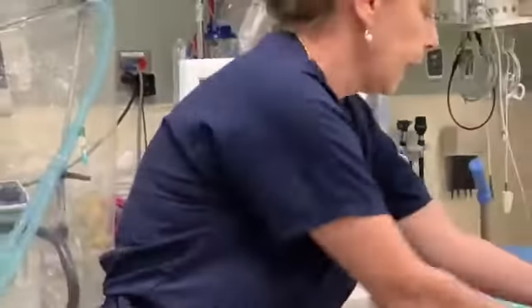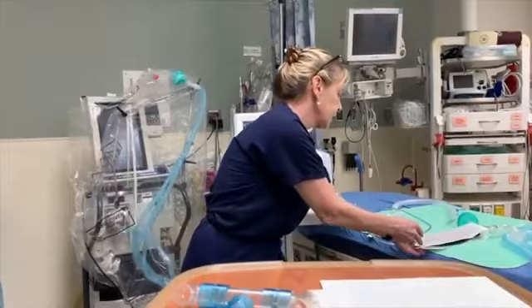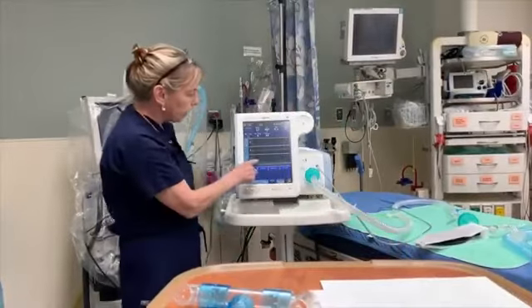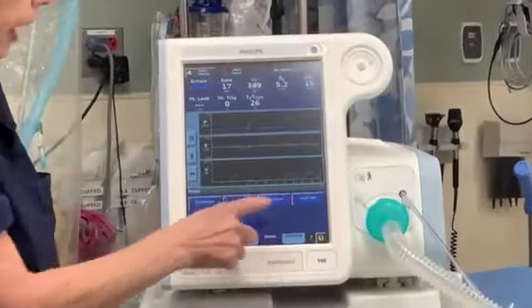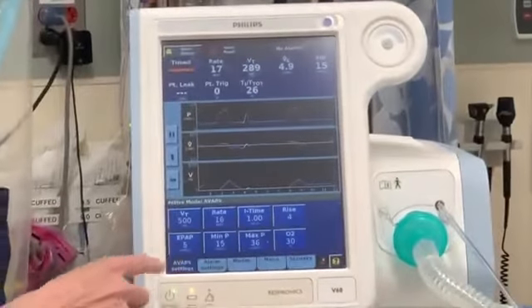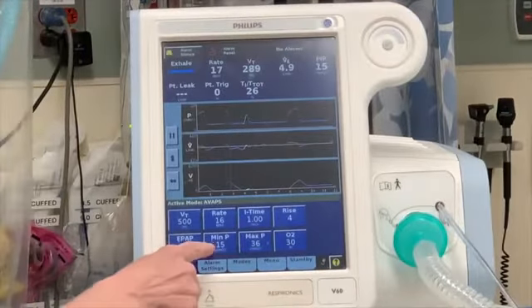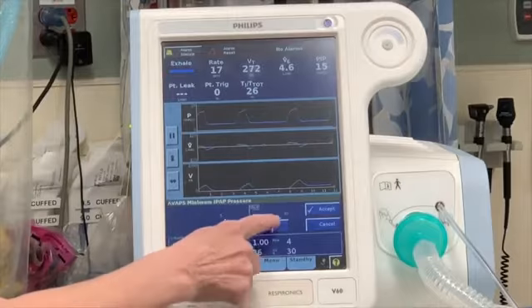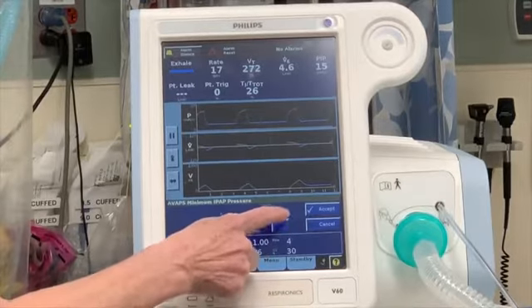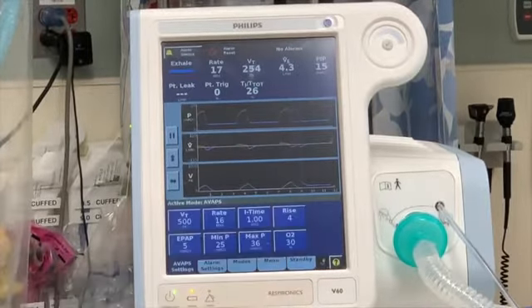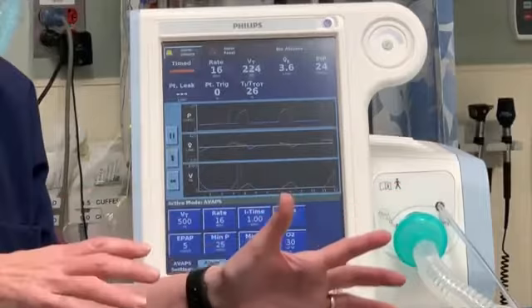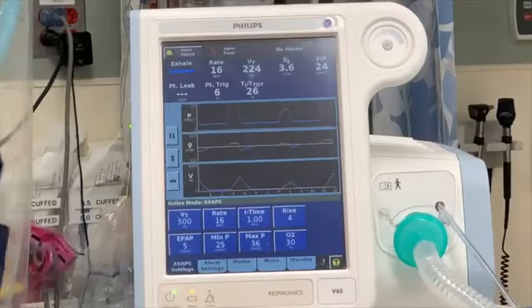So now it's working. I'm going to put this back into its non-compliant mode, so it's ARDS. And you can see here, we're not quite at the peak of 500. And that's because it uses a rolling average in the pressure. So the minimum pressure is 15. If I take that minimum pressure and go right up to 25, then accept, the next breath will be at 500. And that's because with the rolling average, the machine will slowly get up to 500, but it may take too long, and you don't want it to take too long.